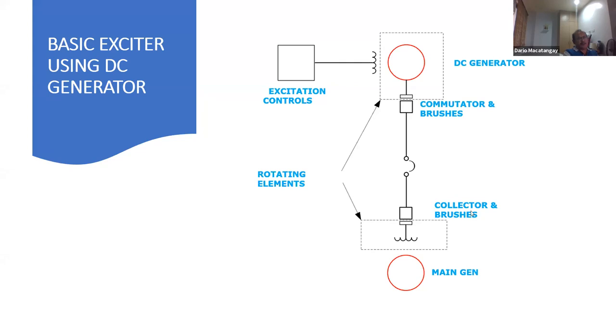Now remember, if it is an AC generator, it's collector rings and brushes. If it is a DC generator, it's commutator and brushes. Now you would need excitation controls. This is where your AVR is located. The AVR is important in the control of voltage, because you need to control the flow of megavars. Megavars is the inductive energy needed to maintain synchronism with the system. Because if you don't have this magnetic field, you can be out of synchronism and then you actually damage the generator, right? So the excitation system is very important in the process, and we need to protect this system along with the generator.